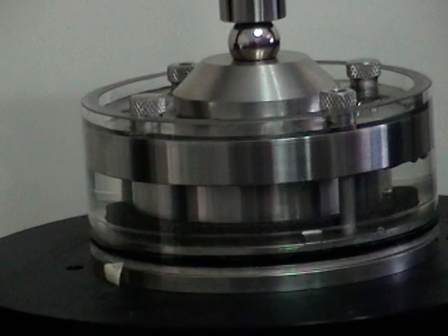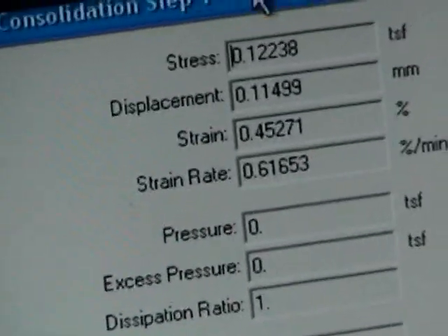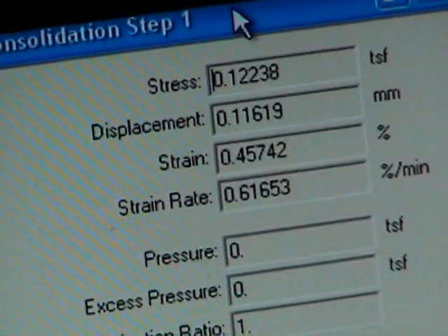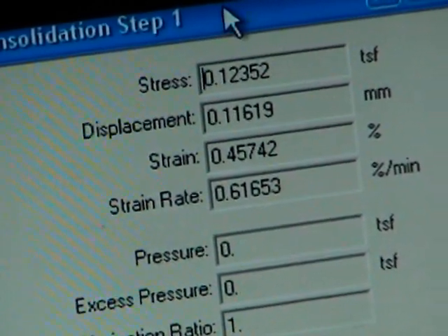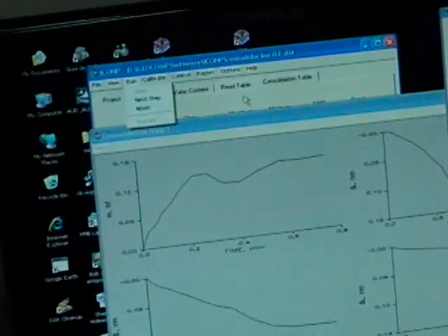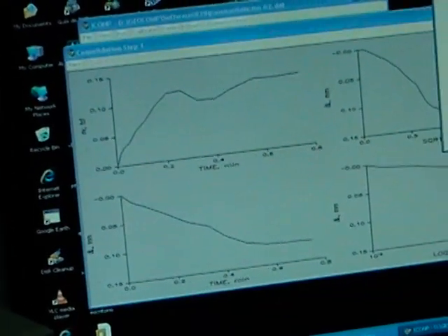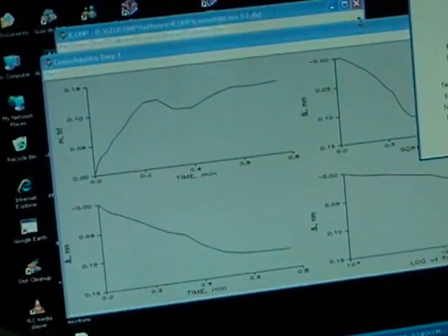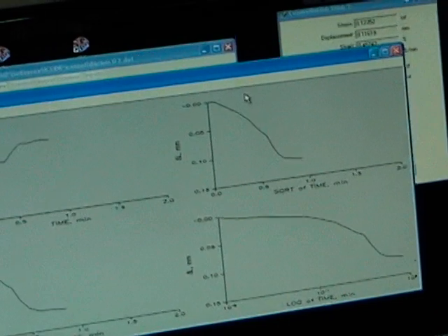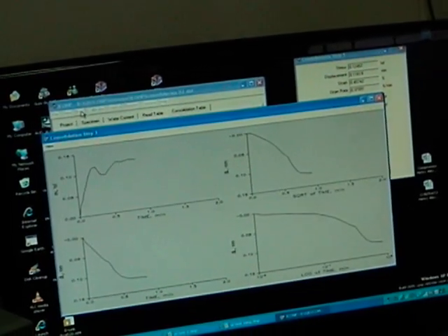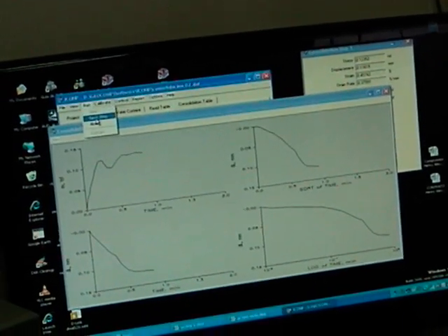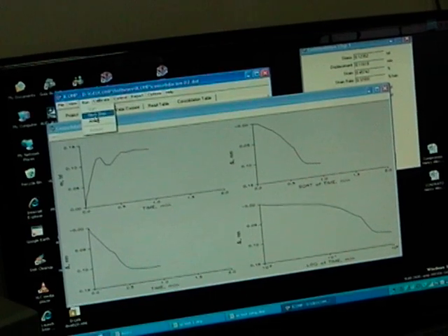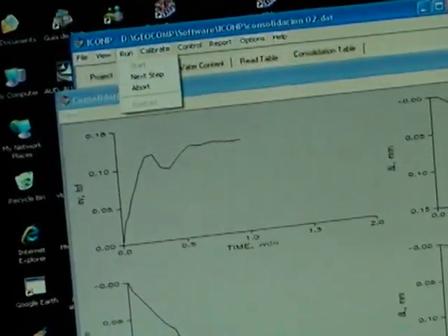Now what we're going to do, we're going to look at the test. If the sample starts to swell, we need to go or make it to the next step. What we can do is go Run and do Next Step. You should not, according to the standard, you should not let the sample swell. This sample is not swelling, we're okay here. But if it does, you go to Run and do Next Step so you don't let your sample swell.